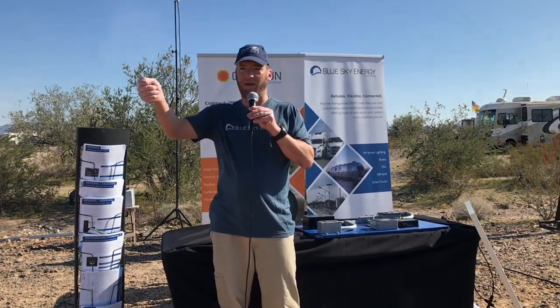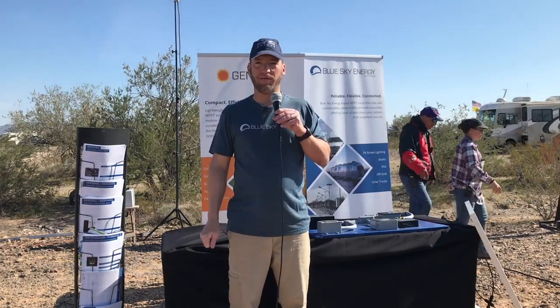Bad panels tend to give almost no power, almost zero current. So a lot of times you'll test each panel, say 5 amps on this panel, 3 amps on that panel, 5 amps on another panel. You should have 13 amps at the bottom. Then they reconnect these MC4s, test at the bottom, and get 2 amps. That means bad MC4s, chop them out. Solder and heat shrink never goes bad.